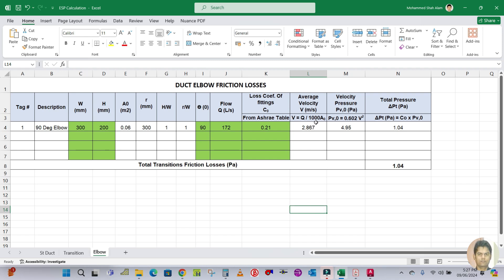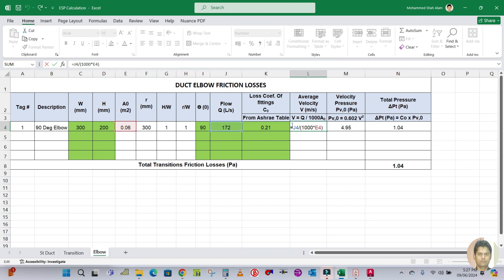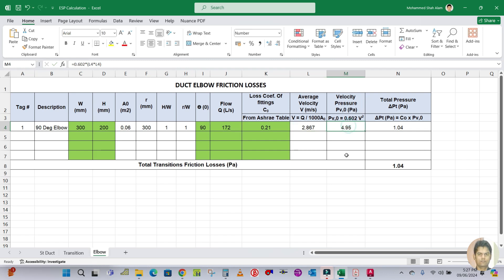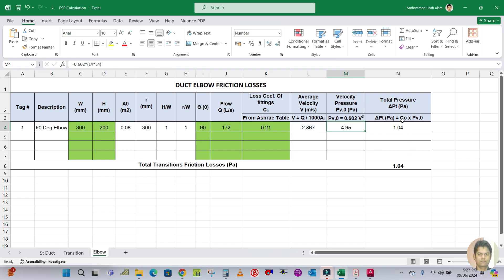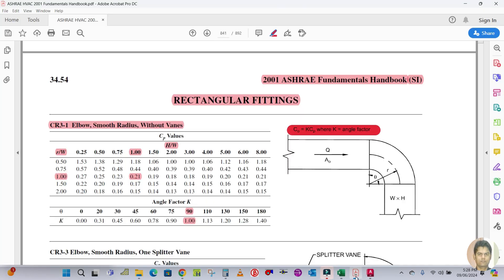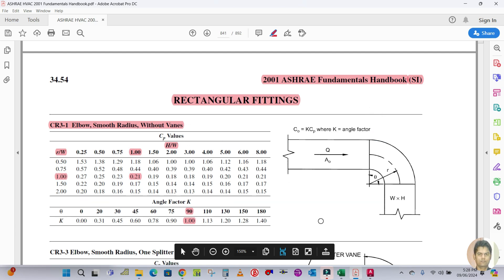Average velocity equals flow divided by 1000 times area (E4). Velocity pressure equals 0.602 times V squared — with V equal to 2.867 m/s. Total pressure drop equals velocity pressure times the loss coefficient Co. The result is 1.0 Pascal. This is how we calculate the pressure drop for a 90-degree elbow.